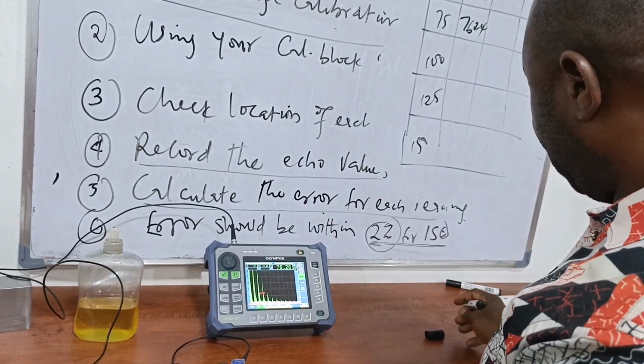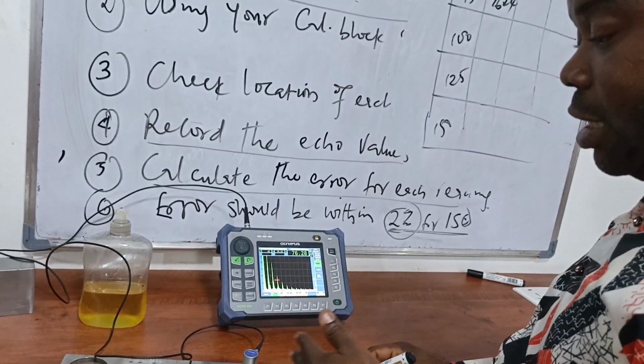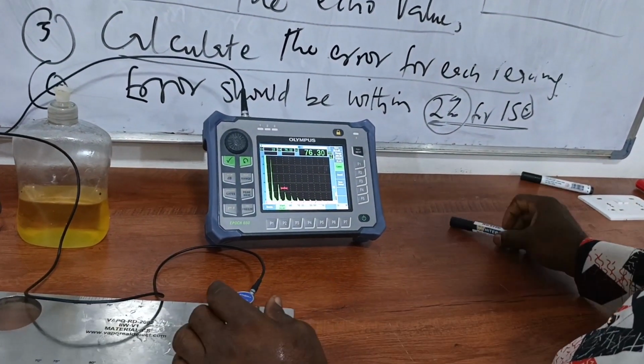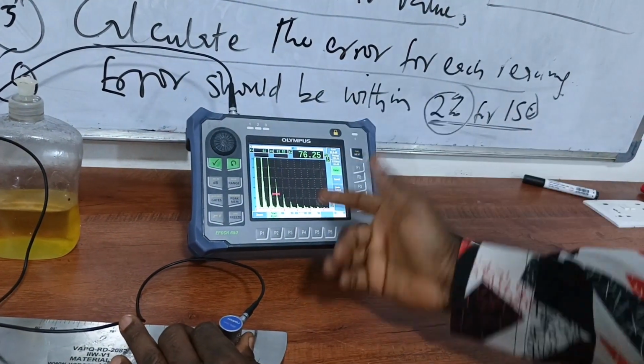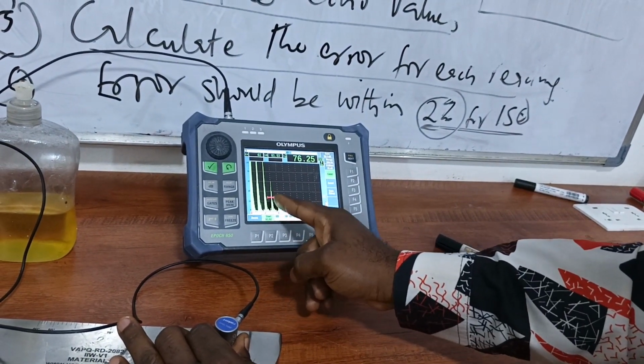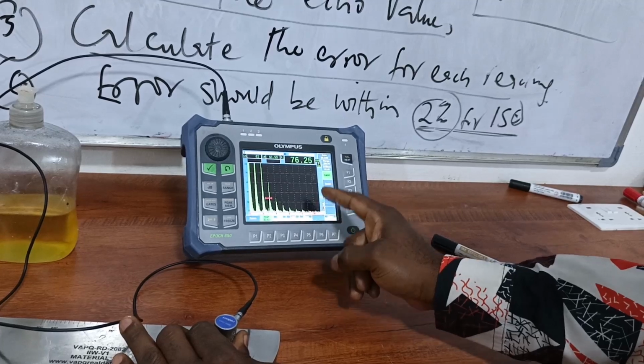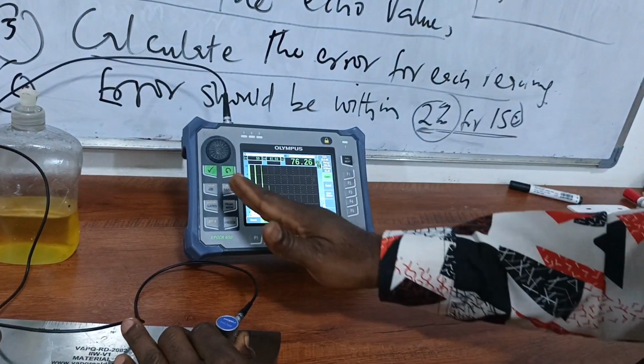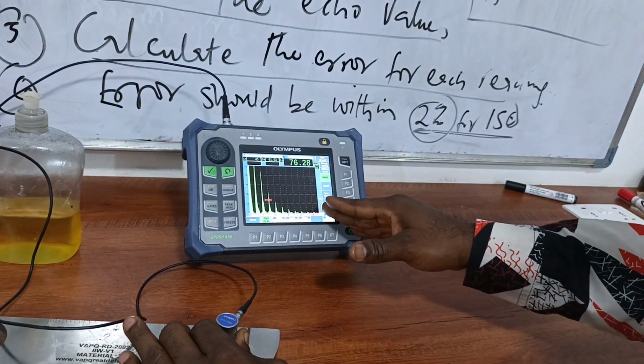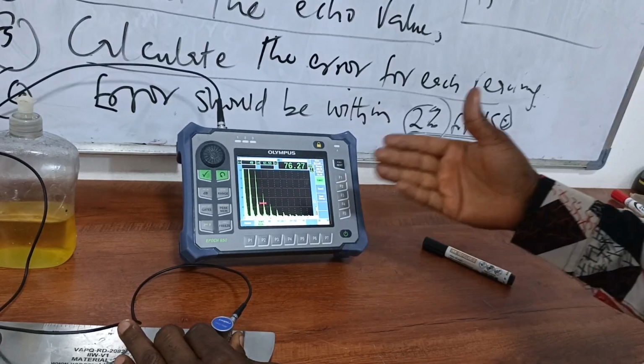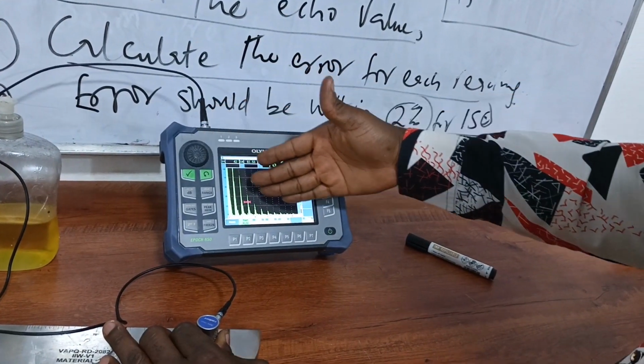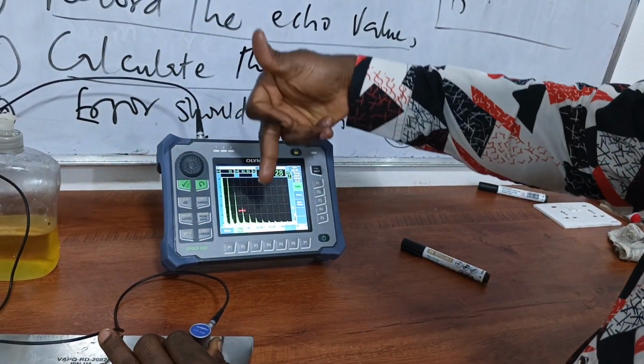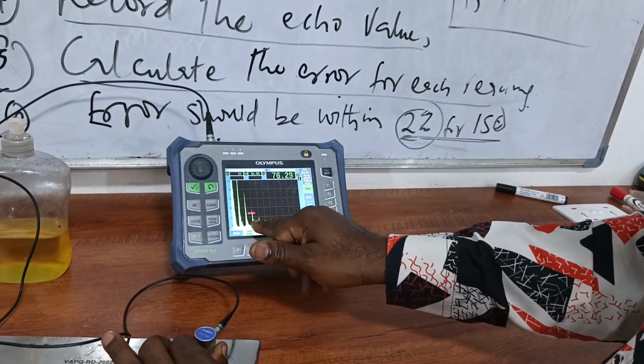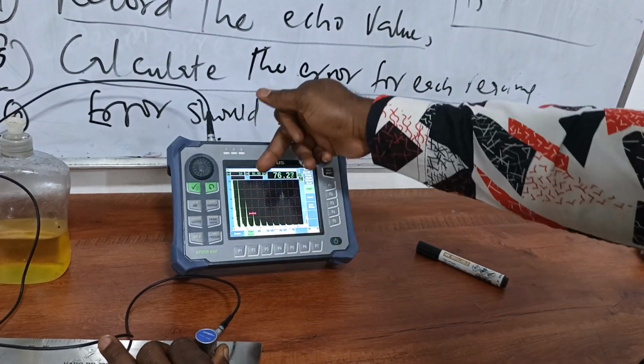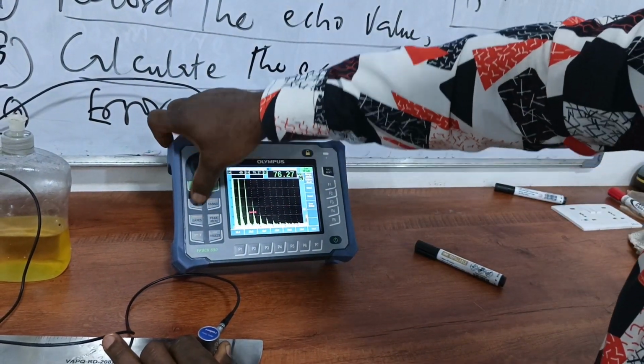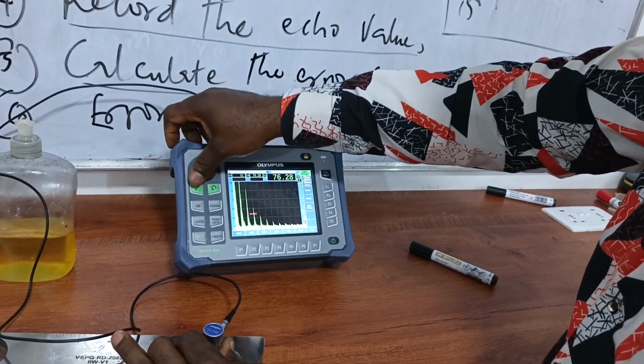If you look at the screen very well, you will see that even before you start reading, you try and count your echoes. You see 1, 2, 3, 4, 5, 6, 7, 8, 9, 10. It means it's giving you the right echo. As you move down towards the 10th echo, you will see that the amplitude is dropping. So by the time you get to about the 4th, 5th, 6th one, where the amplitude would have dropped, please go to your gain and increase gain.